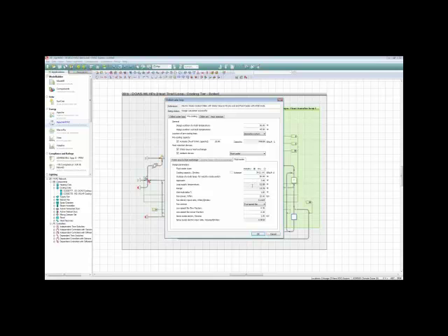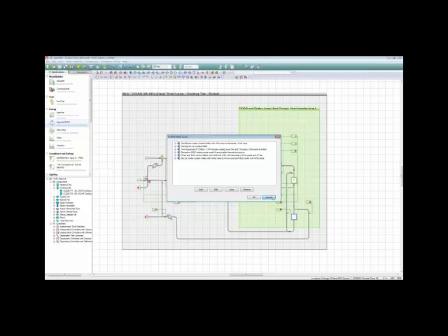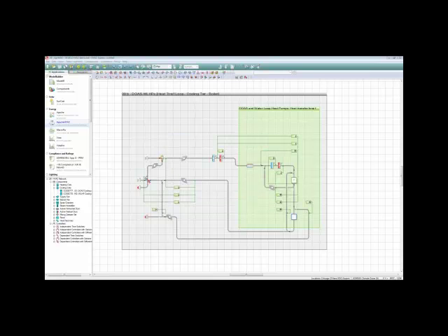And this fluid cooler can operate with pretty much the same design parameters, and so forth. But I have this parameter up here for the auto size percentage of the chilled water loop capacity. So this device can be seen as sort of a smaller cooling device on the loop that's attempting to do the same thing as the chiller before the load ever gets to the chiller. All right. That's probably enough for the water side, so I'll take a few minutes just to demo some of the other things in terms of editing systems and moving things around.